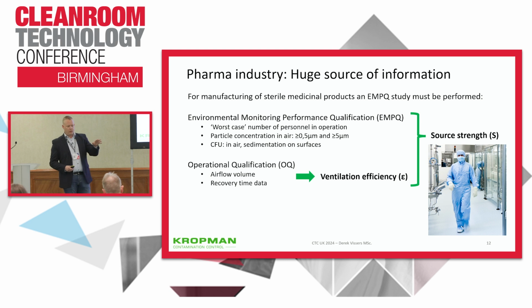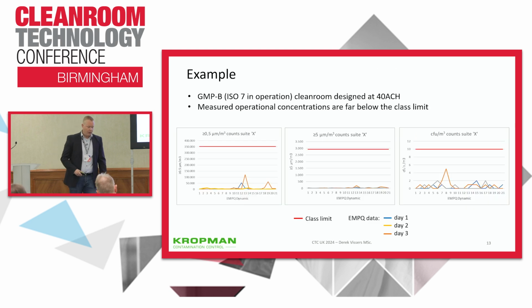Then you measure the particle concentrations, but also the CFUs in the air and sedimentation on surfaces. If we combine that with our operational qualification data, you can calculate the actual source strength in your clean room. Because during operational qualification, you determine the airflows, but also the recovery times at different locations in your clean room. Based on this data, you can calculate the actual ventilation efficiency, and combining this with the EMPQ data gives you the source strength during the EMPQ. I will show you an example.